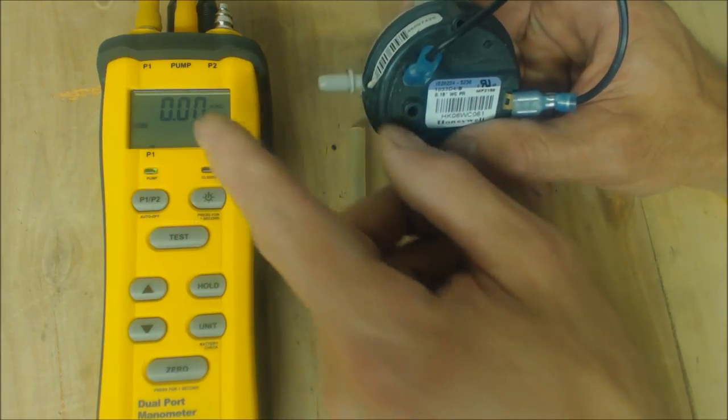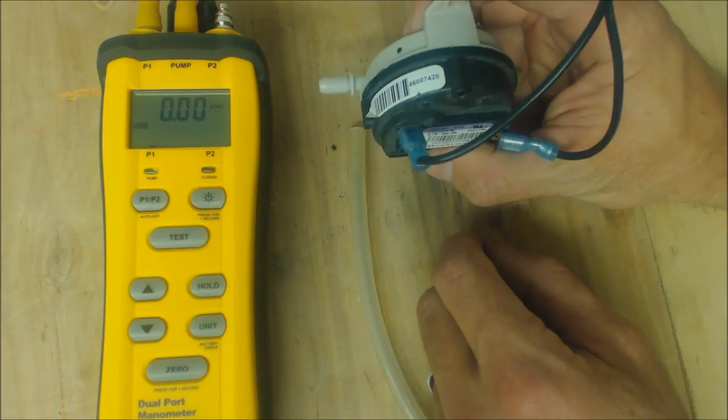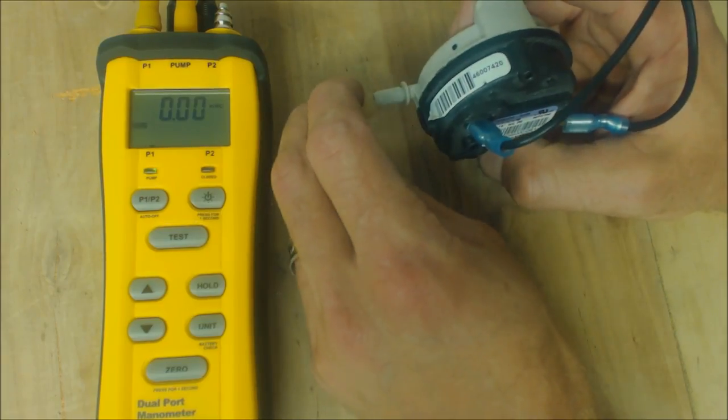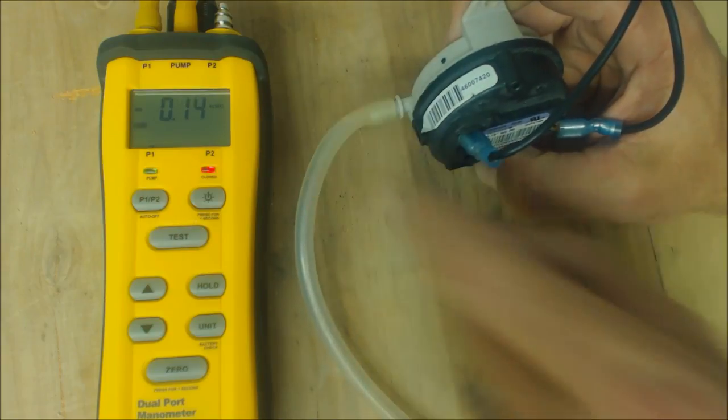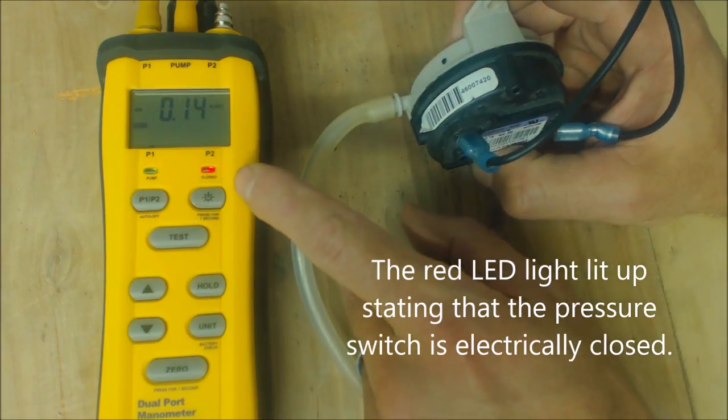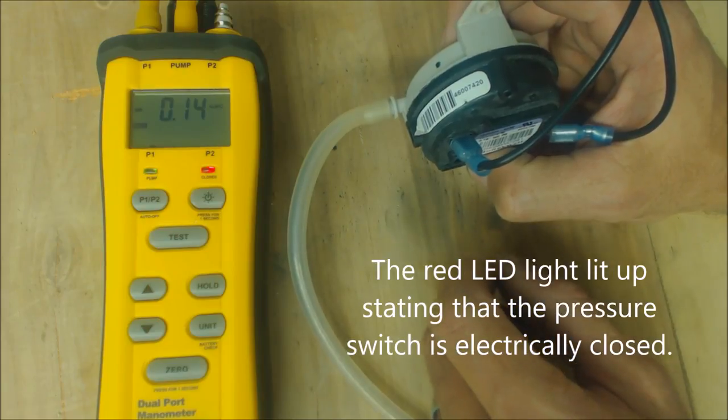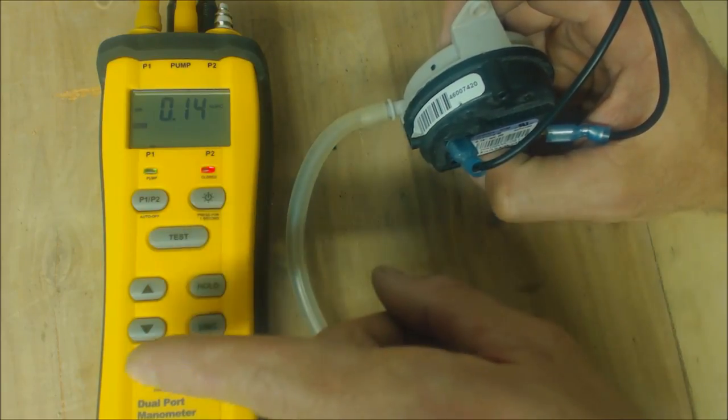We have the hold button flashing. We're going to turn the pressure switch vertically like the way it would be in a furnace and attach this. Right there it said it closed at 0.14. Now we're going to see what it's going to open at, meaning when it opens the electrical circuit.